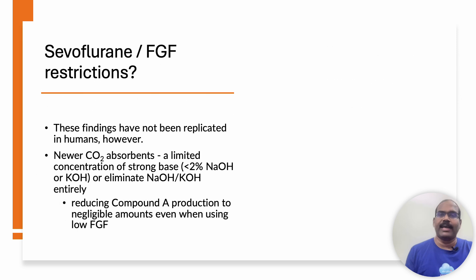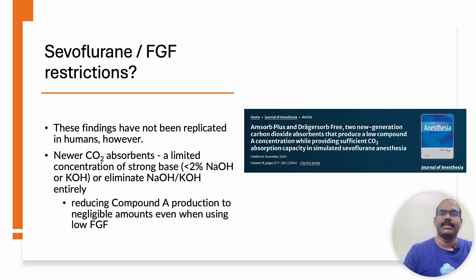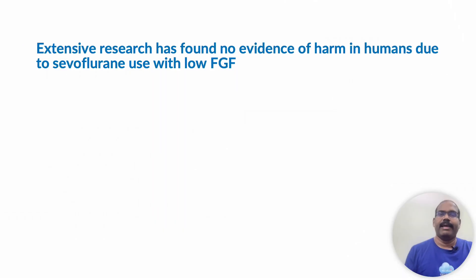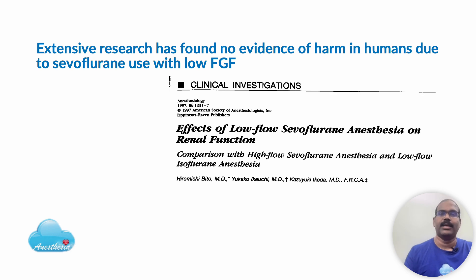The animal study findings have not been replicated in humans, however. Some CO2 absorbents currently on the market were designed to have a limited concentration of strong base — less than 2% of sodium hydroxide or potassium hydroxide — or eliminate sodium or potassium hydroxide entirely, reducing Compound A production to negligible amounts even when using low fresh gas flows. Extensive research has found no evidence of harm in humans due to sevoflurane use with low fresh gas flows.